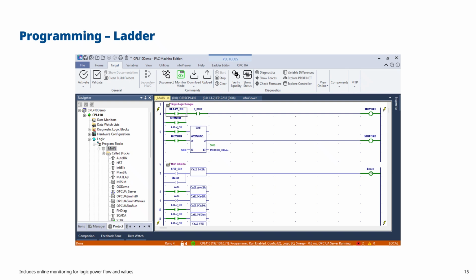What you can see on that main program is that when the reset button is pushed or when the first scan happens, we call an initialization block. At the end of that, it turns off the reset. There's a reset coil to turn off the reset input, so that's like a one-shot. But we have also got one-shot contacts. And then we've got lots of other contacts and function blocks you can use to perform your operations.